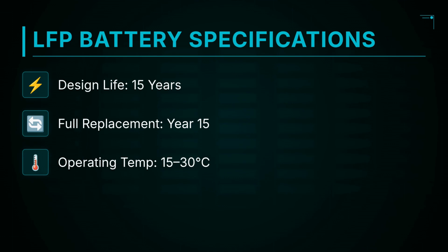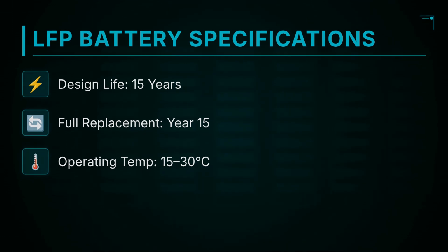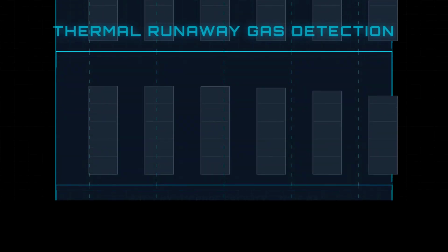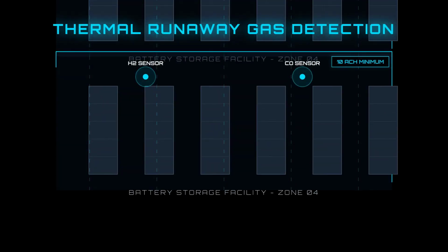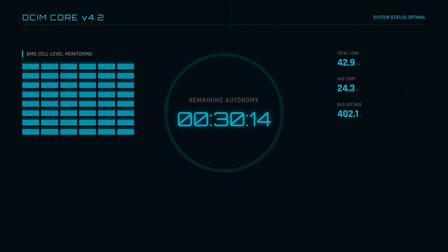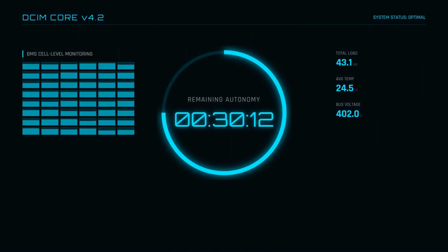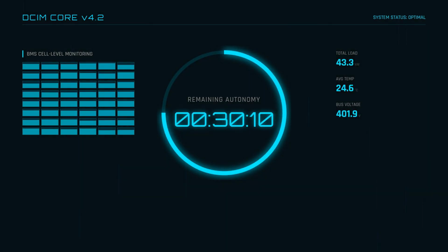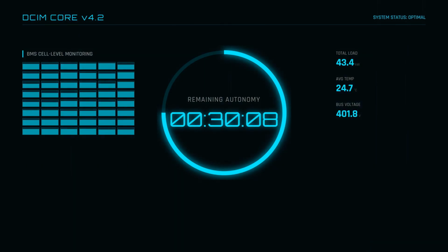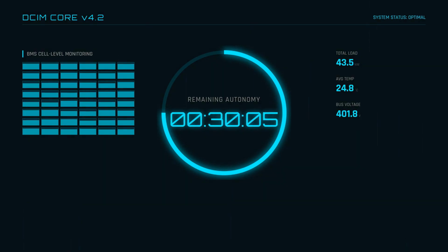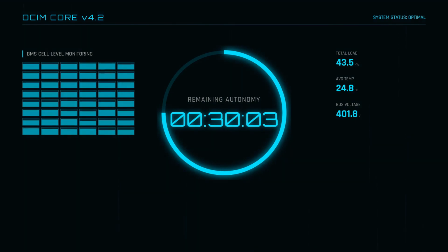We maintain operating conditions between 15 and 30 degrees Celsius to maximize performance. Each battery room has dedicated HVAC providing 10 air changes per hour minimum. We monitor for thermal runaway gases, specifically hydrogen and carbon monoxide, with high sensitivity integrated sensors tied to the emergency shutoff. BMS monitoring tracks every single cell's voltage and temperature. This data feeds into our DCIM in real time, allowing our operations team to track remaining autonomy down to the exact second for total situational awareness.